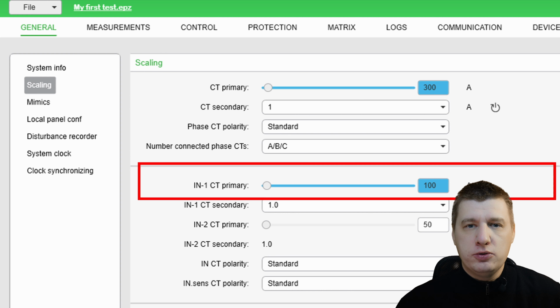This setting is for phase current transformers. These are three sensors that monitor the main load current flowing through your L1, L2 and L3 lines. If you have a 300:1 CT set on your phases, your CT primary is 300 amps.